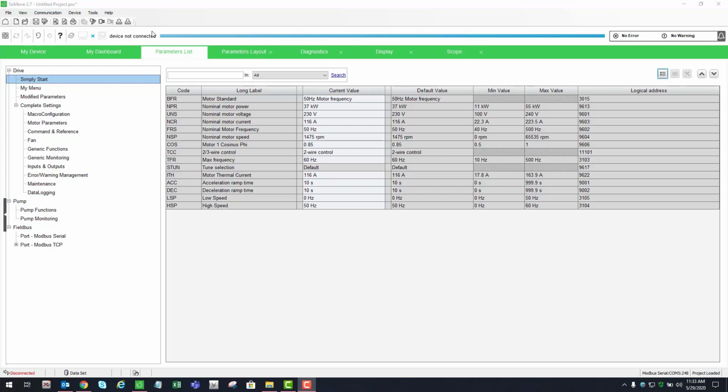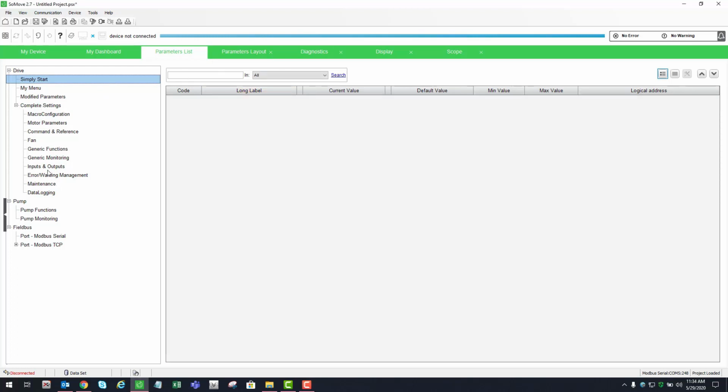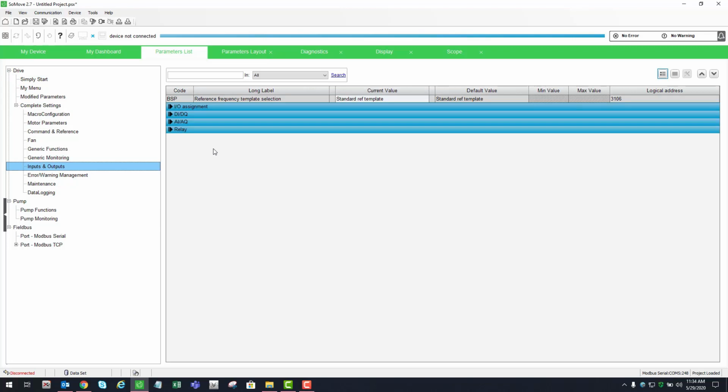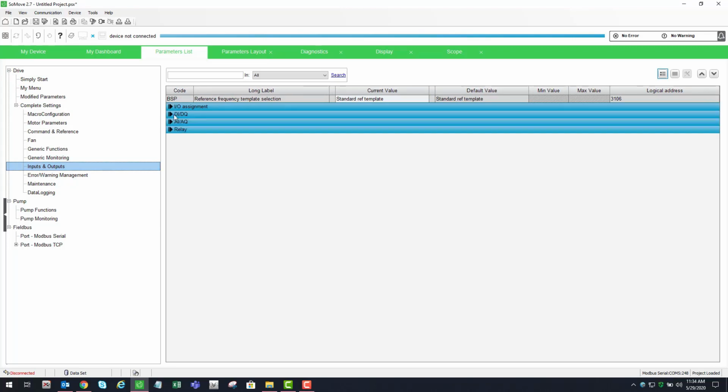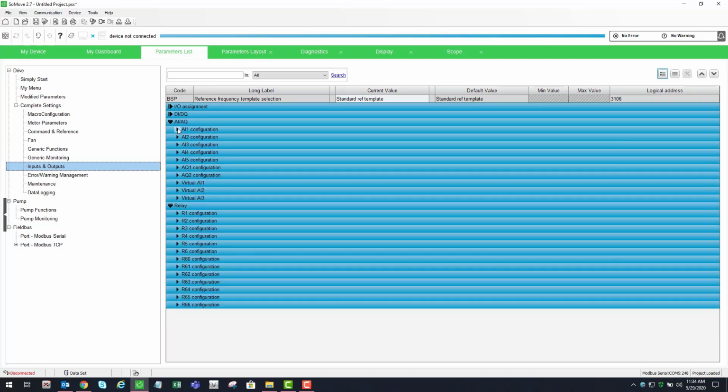But in SoMove, you want to be under the parameter list, and under parameter list, to configure analog output configuration, you need to go into complete settings and go down to input outputs right here. Now under input outputs, you have your analog input assignments here to see what they're programmed as. The relays are here as well, but the one we're more interested in is the analog input and output tab.